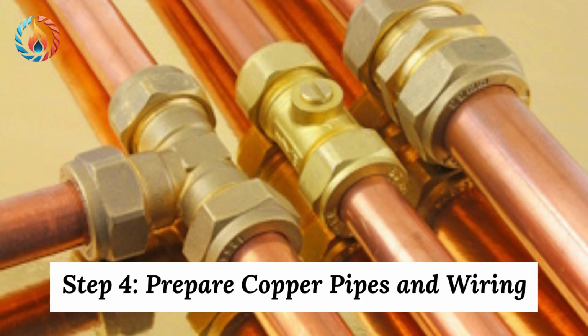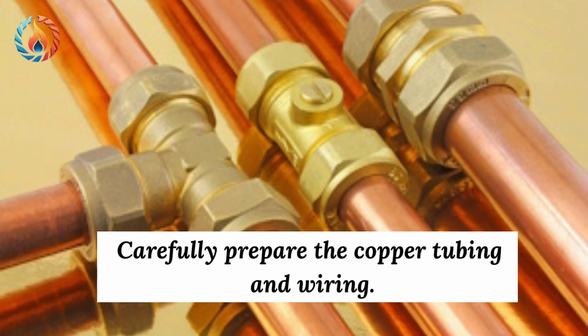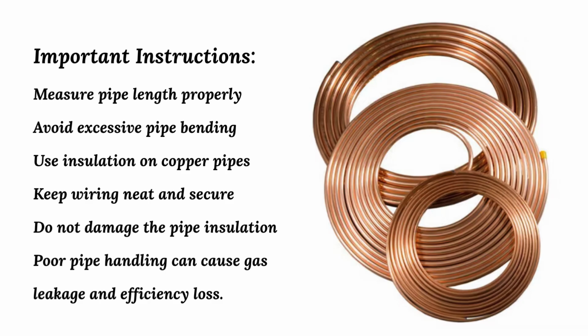Step 4. Prepare copper pipes and wiring. Carefully prepare the copper tubing and wiring. Important instructions. Measure pipe length properly. Avoid excessive pipe bending. Use insulation on copper pipes. Keep wiring neat and secure. Do not damage the pipe insulation. Poor pipe handling can cause gas leakage and efficiency loss.